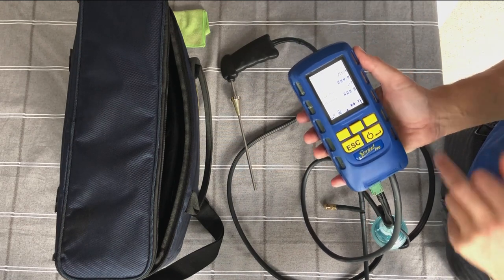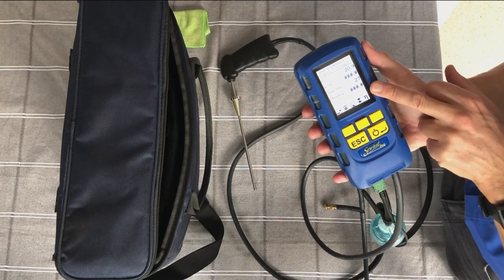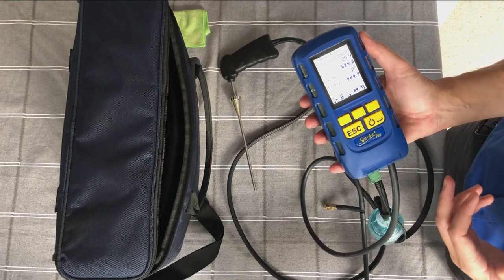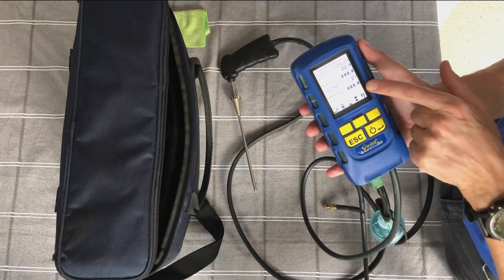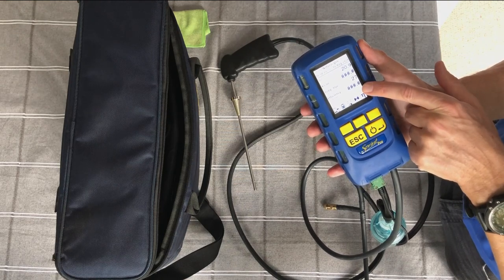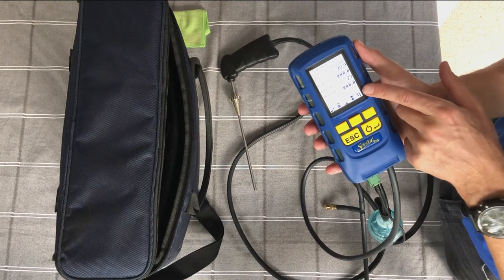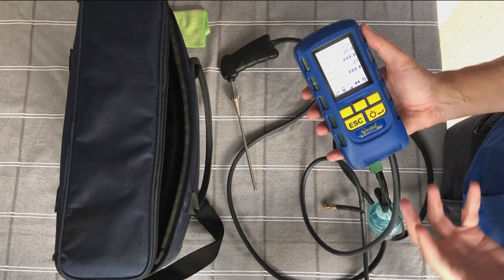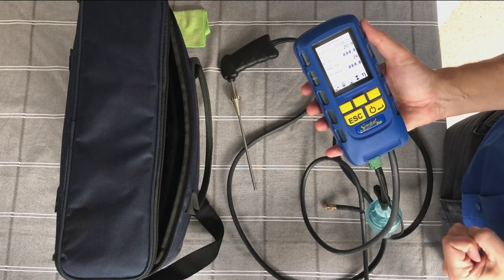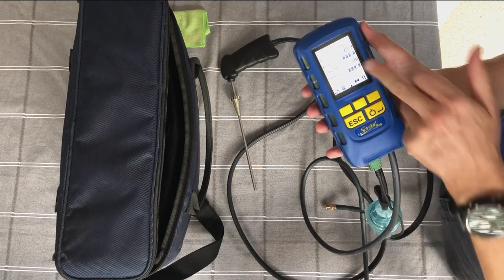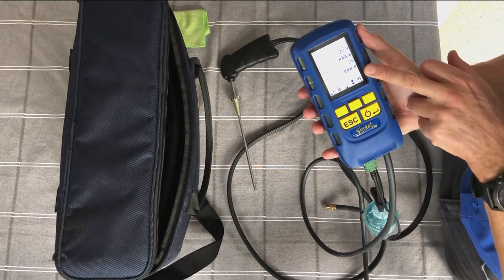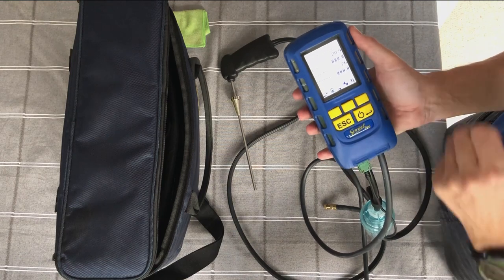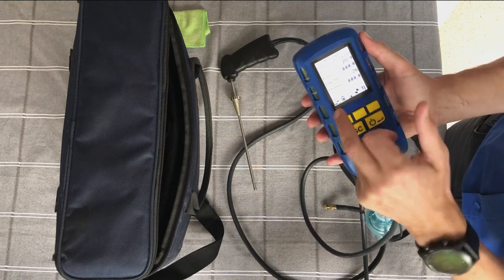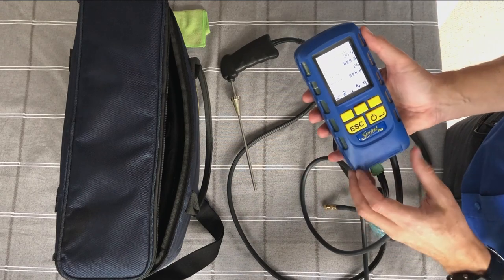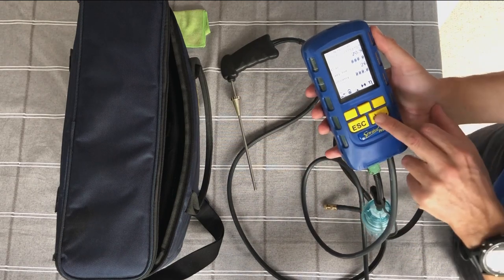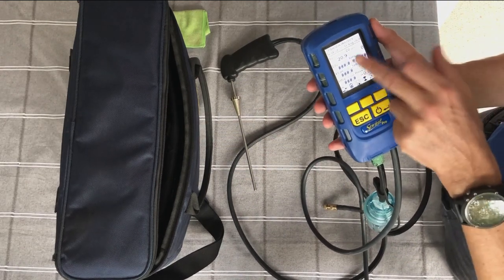And on high efficiency appliances, you can get above 100% efficiency, believe it or not, because of the heat reclaim. So don't think it's something going wrong. If you've got one of these and it shows over 100% efficiency, it's actually correct. It's measuring it correctly, and over 100% is possible. If you're on a standard, non-high efficiency appliance, it won't get above 100, but it will remain in gross rather than in high efficiency mode. If I press it again, now I get everything on one page.